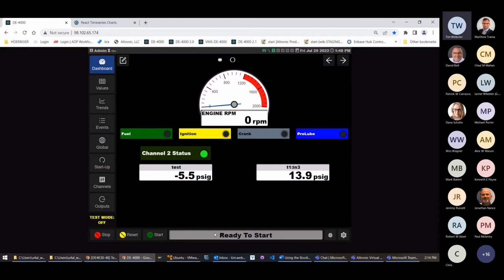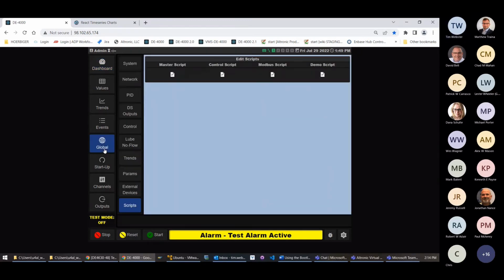But along with that, now we can do custom alarms. I've just got this in the script linked. If I get above 20, it goes to a custom alarm. Now, all you have to do is start your message, your status string, with the word alarm. And then you can put whatever details you want in here. So it's just a simple status string.